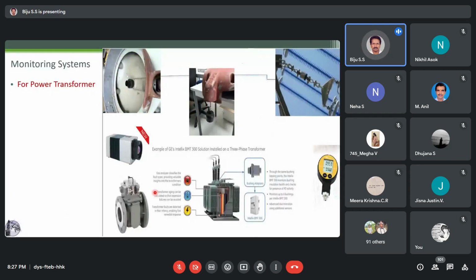And for power transformers, we have different systems available. There are Buchholz relays, which will carry out gas analysis. The system itself will carry out gas analysis and indicate the fault type, which is the latest thing available in the power transformer. We used to have traditional Buchholz relays, but nowadays Buchholz relays have become intelligent by themselves, and it gives out the transformer condition. Whenever a tripping happens, it will analyze the gas itself and give out trending information on these things.